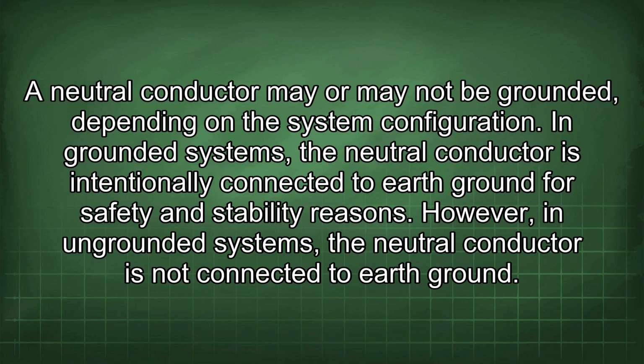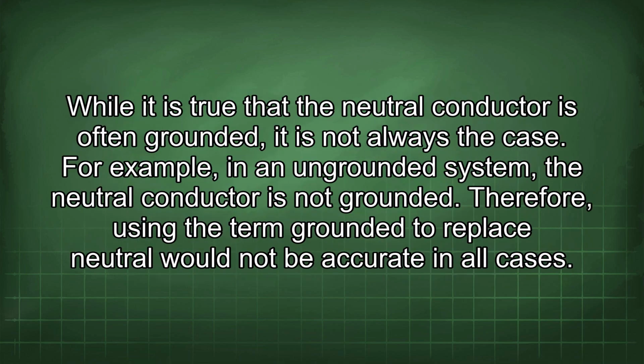In grounded systems, the neutral conductor is intentionally connected to earth ground for safety and stability reasons. However, in ungrounded systems, the neutral conductor is not connected to earth ground. While it is true that the neutral conductor is often grounded, it is not always the case. For example, in an ungrounded system, the neutral conductor is not grounded. Therefore, using the term grounded to replace neutral would not be accurate in all cases.